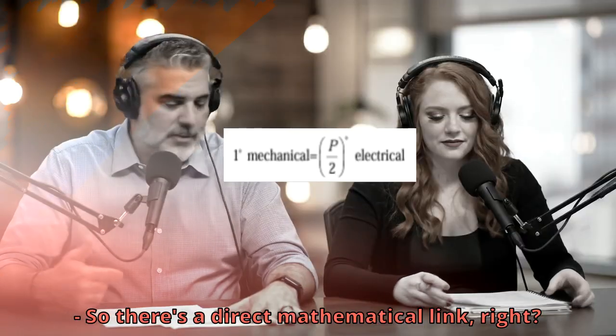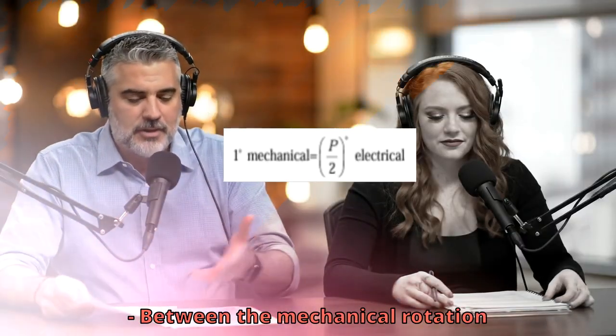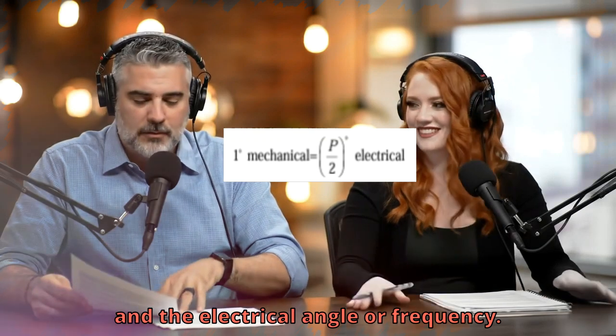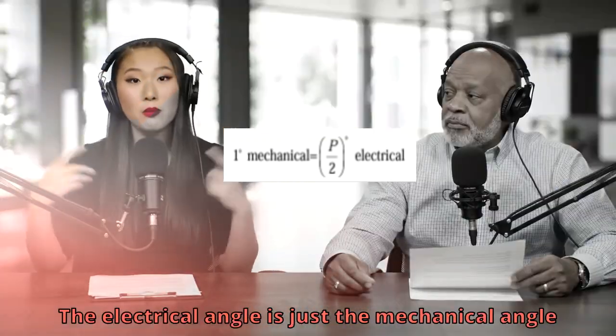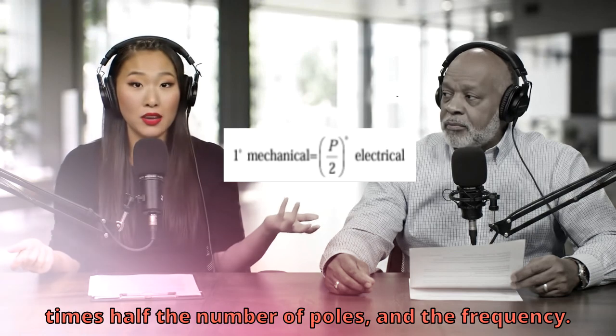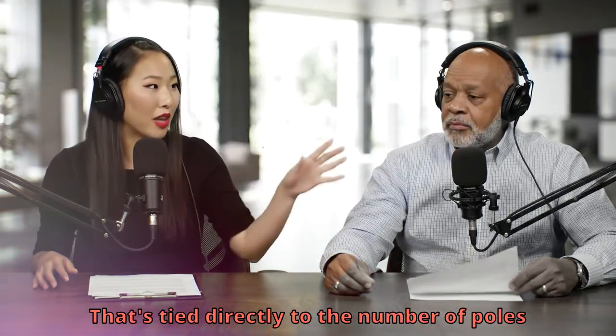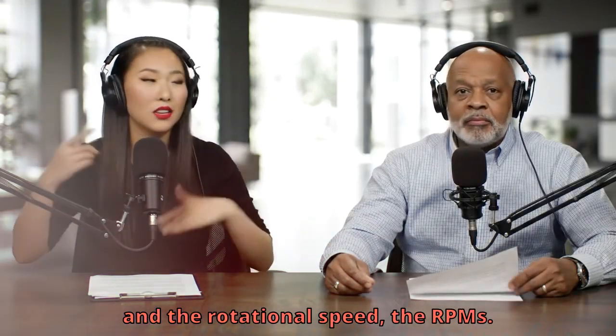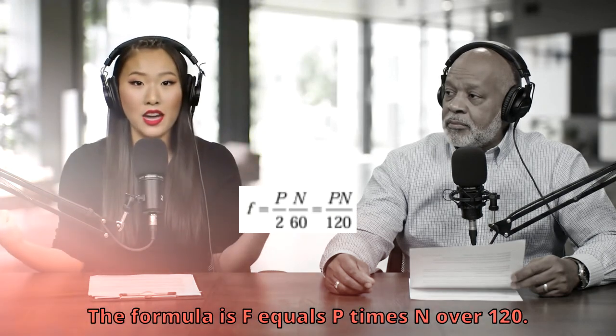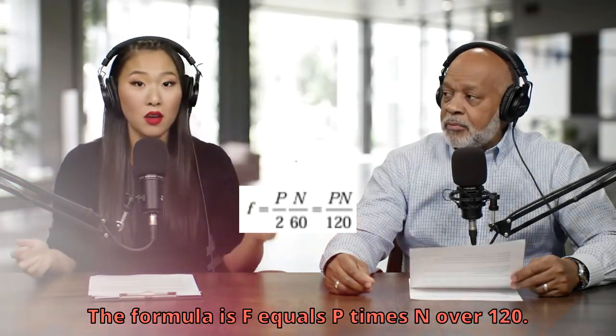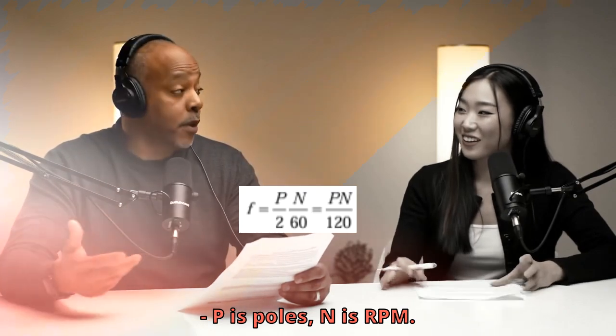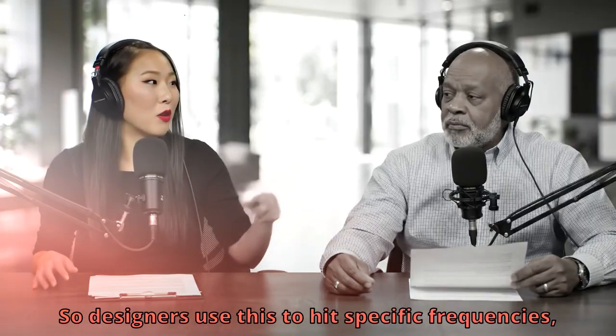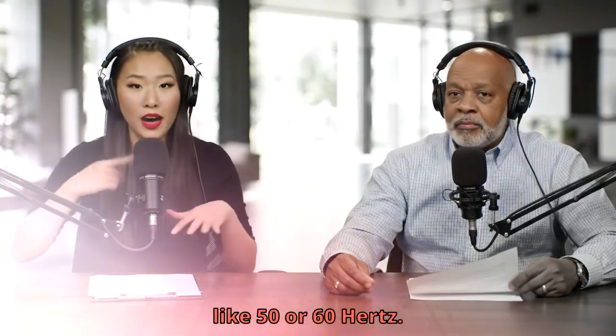So there's a direct mathematical link, right? Yeah, between the mechanical rotation and the electrical angle or frequency. Oh, definitely. The electrical angle is just the mechanical angle times half the number of poles. And the frequency is tied directly to the number of poles and the rotational speed, the RPMs. The formula is F equals P times N over 120. P is poles, N is RPM. Got it. So designers use this to hit specific frequencies, like 50 or 60 hertz.